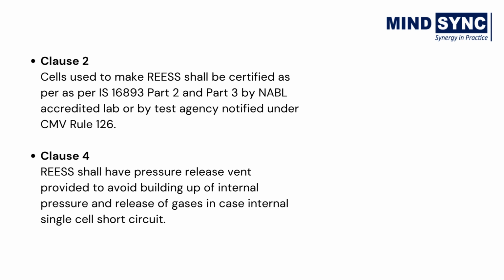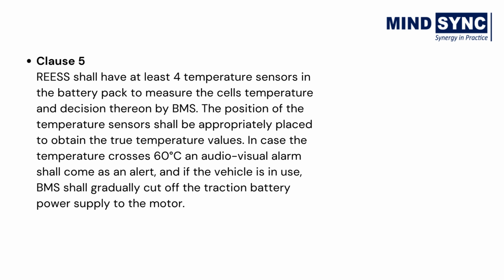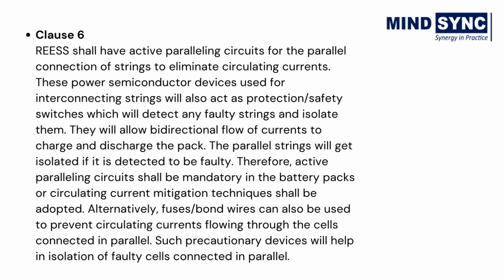Cells used shall be certified as per IS 16893 Part 2 and Part 3. Battery must have a pressure release vent provided to avoid building up of internal pressure and release of gases in case of an internal single-cell short circuit. Battery shall have at least 4 temperature sensors in the battery pack to measure the cell's temperature and decision thereon by BMS. Battery should also have active paralleling circuits for the parallel connection of strings to eliminate circulating currents.